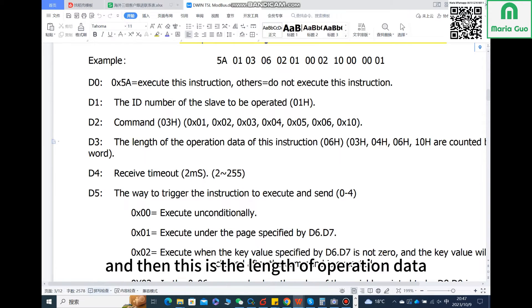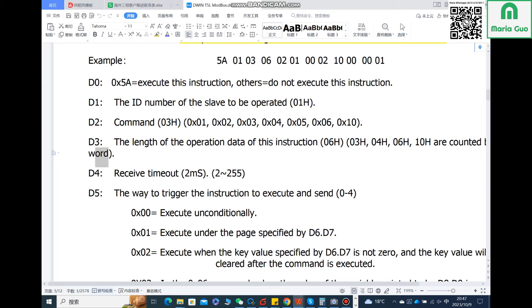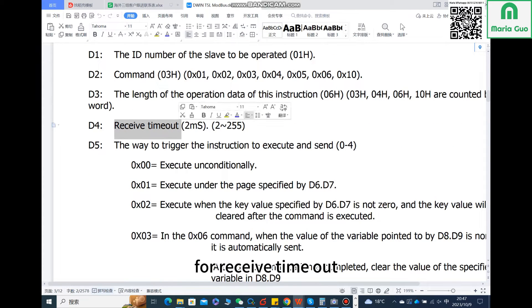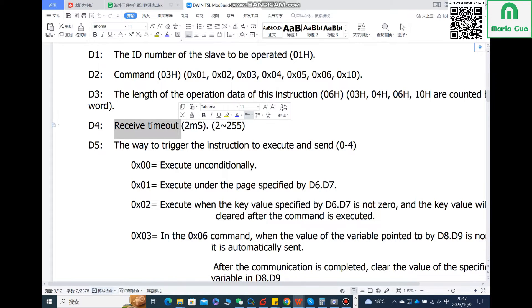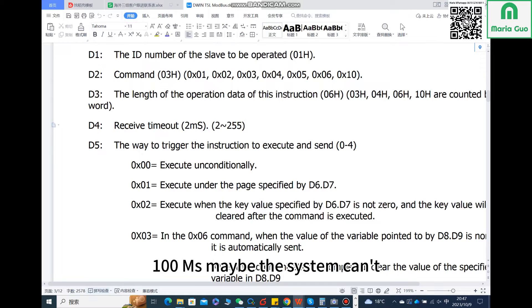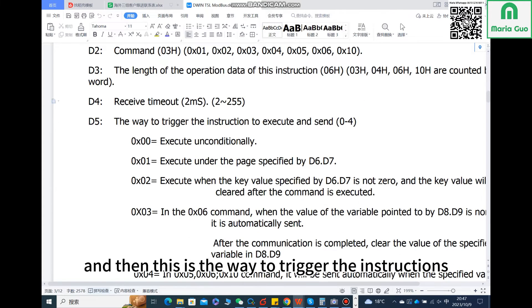And then this is the length of operation data of this instruction. After that is receive timeout. For receive timeout you better set the time more than 100 milliseconds, because I have tested if less than 100 milliseconds maybe the system can't run it correctly.